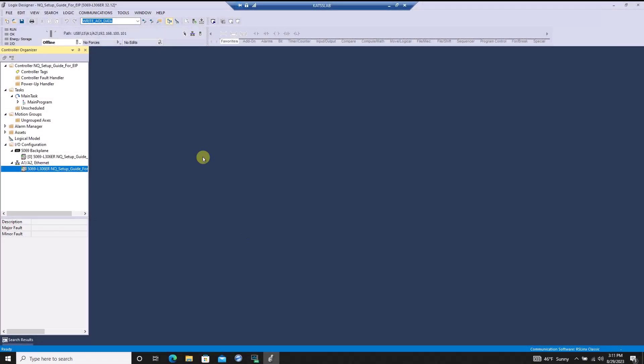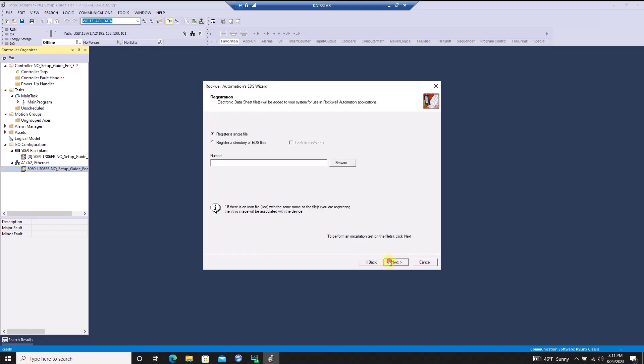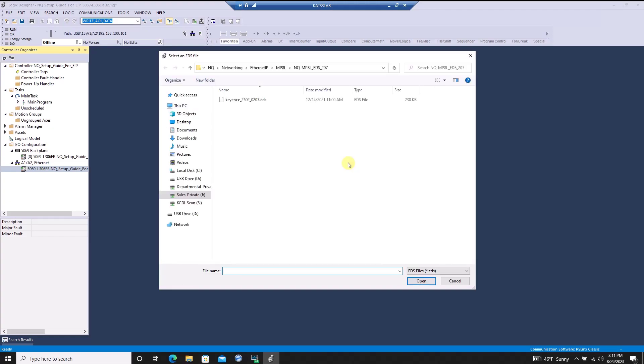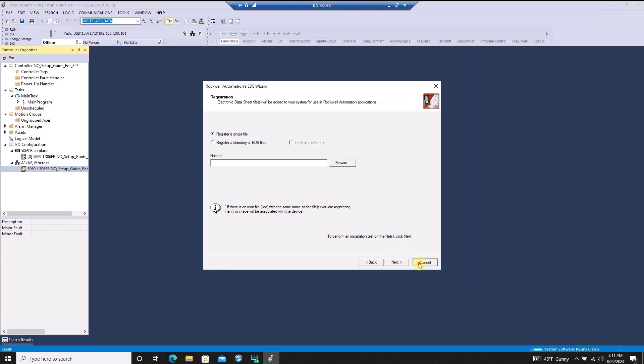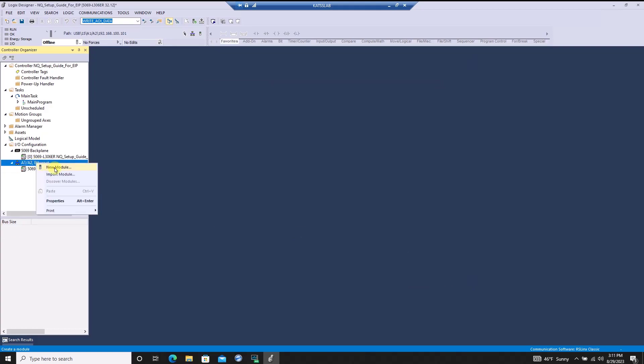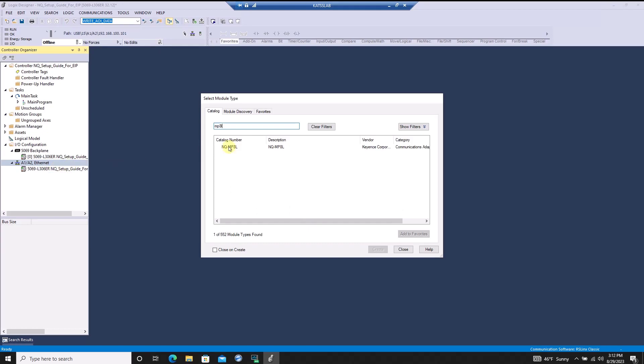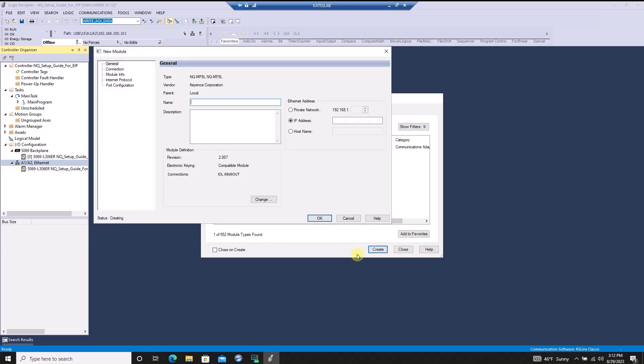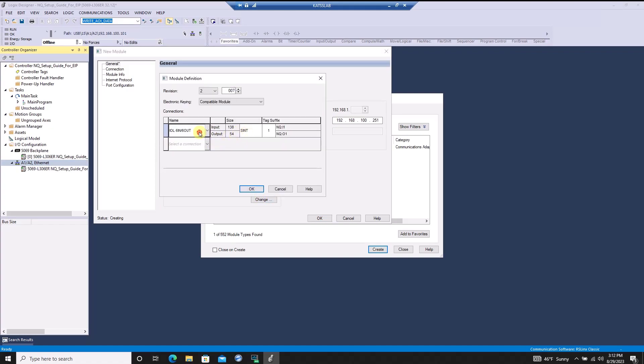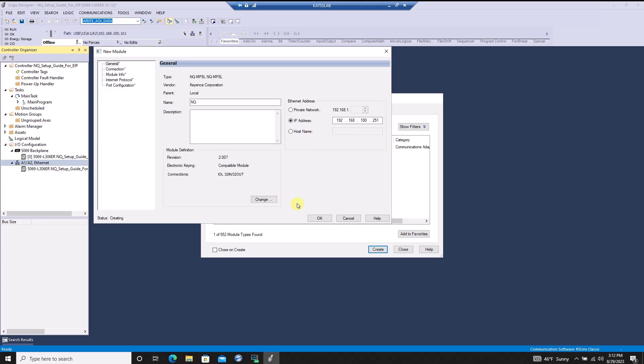I've got a fresh Studio 5000 program open, and I'm going to start by adding the EDS file for the NQ to the PLC software. Once this is done, I can create a new module and search for the NQ model being used. I'll give it a name and the correct IP address, and before I make the module, I want to change two of the module settings to avoid any issues down the road. I'm going to select a process data sizing of 32 in and 32 out, and I'm going to change the module data type to integer. Once I've made the changes, I'll press OK and create my module.